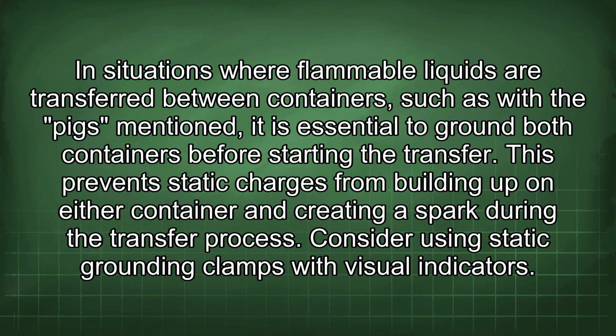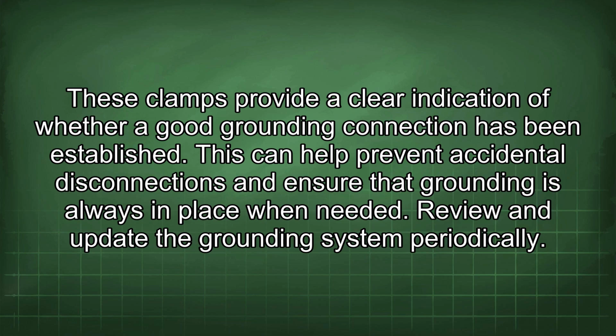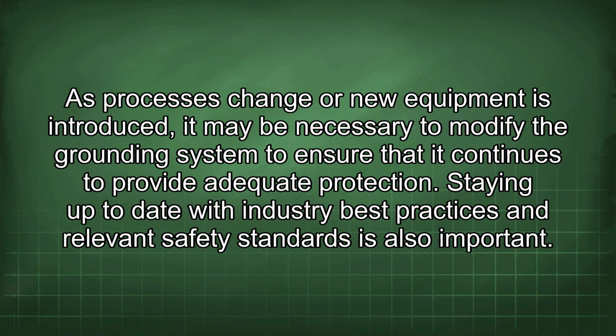Consider using static grounding clamps with visual indicators. These clamps provide a clear indication of whether a good grounding connection has been established. This can help prevent accidental disconnections and ensure that grounding is always in place when needed. Review and update the grounding system periodically. As processes change or new equipment is introduced, it may be necessary to modify the grounding system to ensure that it continues to provide adequate protection. Staying up to date with industry best practices and relevant safety standards is also important.